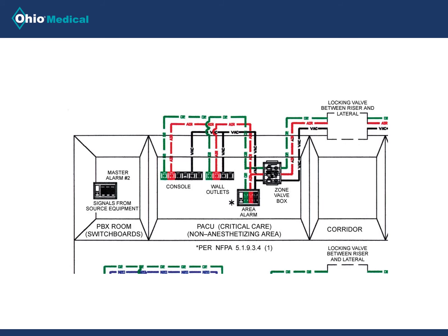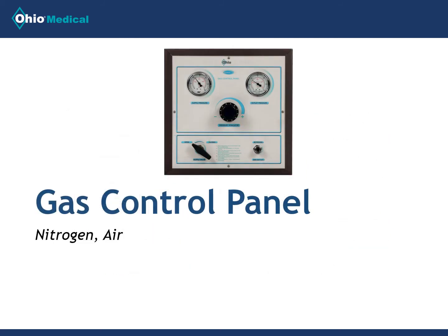Now that we've discussed the alarms and valves, it is time to move into the patient environment. The Ohio Medical Gas Control Panel is available for nitrogen or instrument air. There is one DISS outlet on the front panel and another outlet for routing gas to remote outlets. The panel includes a supply valve, regulator knob, and gauges for supply and regulated pressures. The unit has a pressure range from 0 to 250 psi.